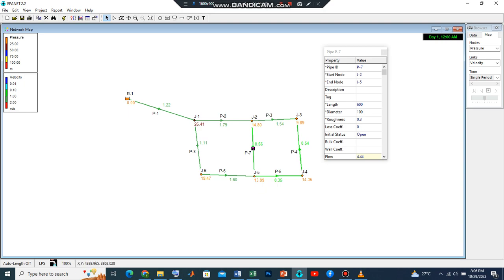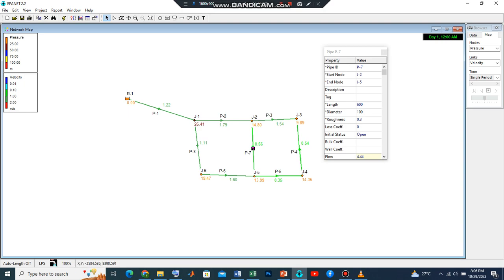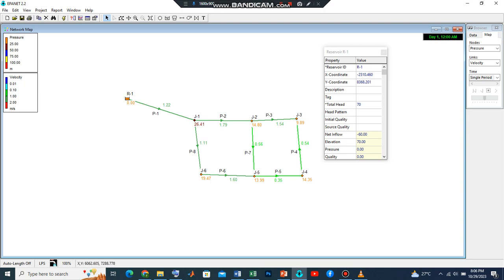What this means is that you need to continue to make adjustments within the network to ensure that it fell within the reasonable values. If it seems to be difficult to achieve, we can always go back here. Remember, the reservoir may be an elevated tank or something, and if you can see here we have a total head of just 70. So the head losses are also playing a role in affecting our target values.